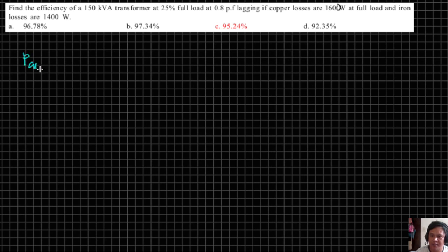PCU at quarter load or load at 25%. No? Full load. So, that is equals to X squared times PCU full load. So, same formula ng kanina. Okay? So, that is 0.25 squared times PCU full load na 1,600. Okay. So, we will get 100 watts.